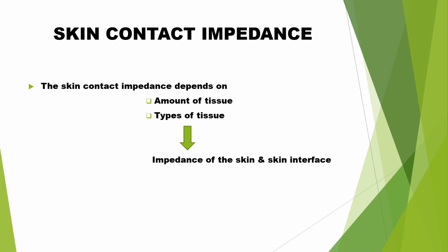The skin contact impedance includes the impedance of the skin and the contact impedance at the skin interface. So the voltage, frequency, current duration, contact surface area, contact pressure, skin condition, and moisture level, all these factors influence the skin contact impedance. It varies widely from thousands of ohms with dry skin and a small contact area to negligible values when the skin's integrity is compromised with lacerations or by heating effects of the current.